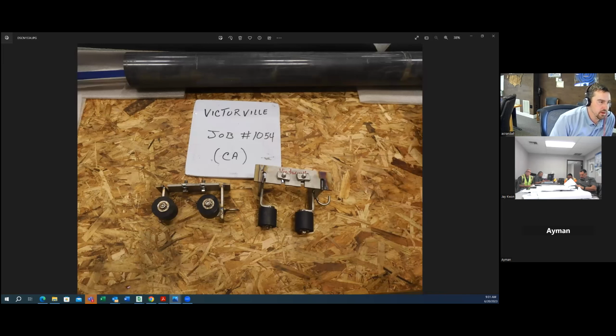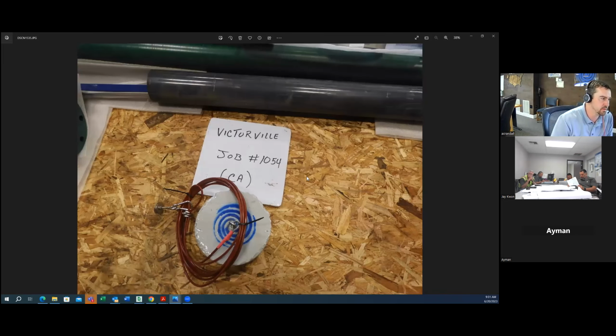This is the upper guide bar bracket that'll go into the nut rail in the hatch, and then your stainless steel piping as your pump guide rails will be installed in the field. We typically ship those long so that you can cut them to length. Every now and then it's hard to get exact on the drawings. Concrete is not always perfect.